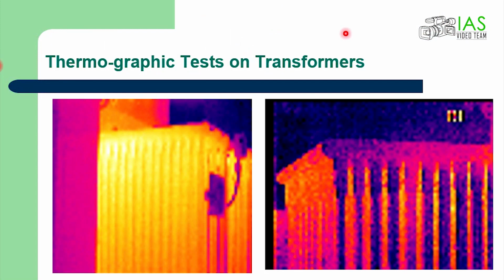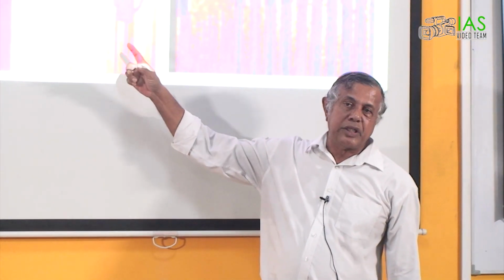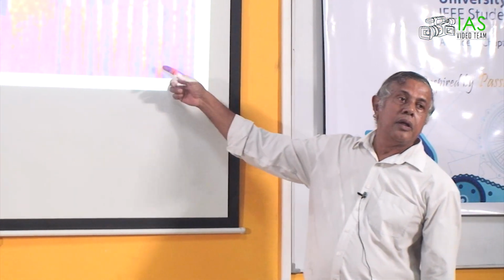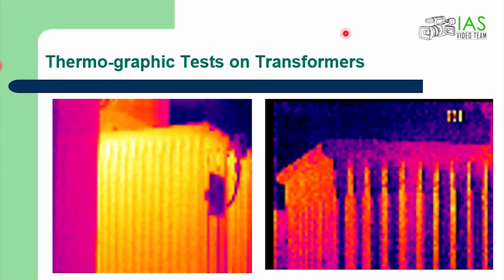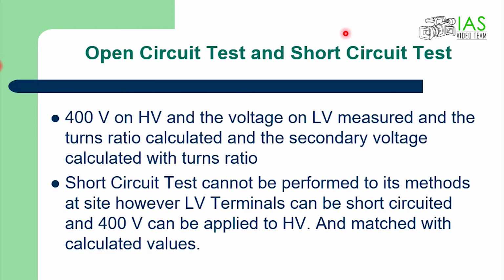So these are thermographic pictures of some transformers. This was taken for a transformer when the fans are not on, at the same loading level. When the fans are on, it comes to this. That means the temperature of the body is higher when the fans are not on. Now, another picture. Yeah, open circuit test and short circuit test, I am not going to talk further about it because it's your basics.